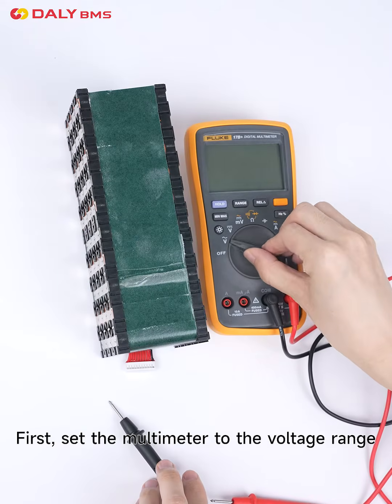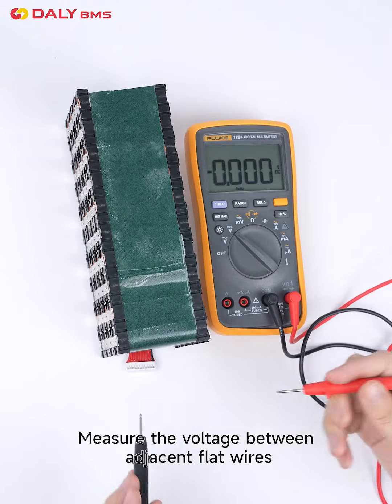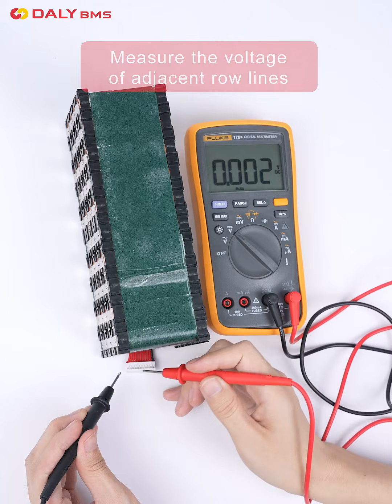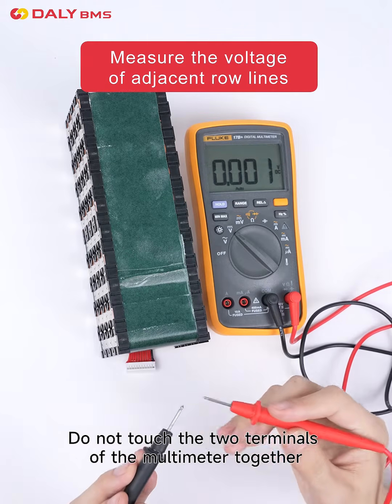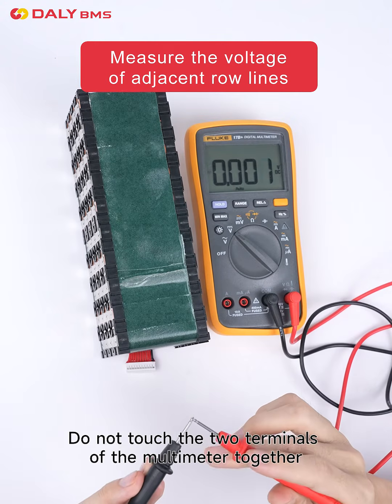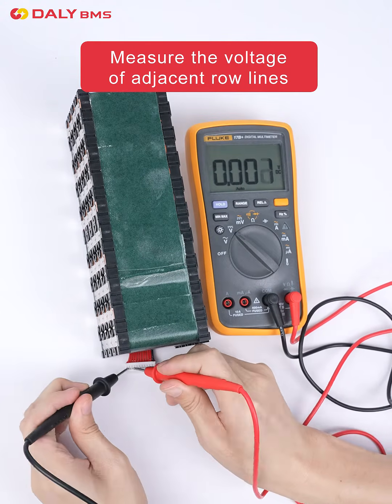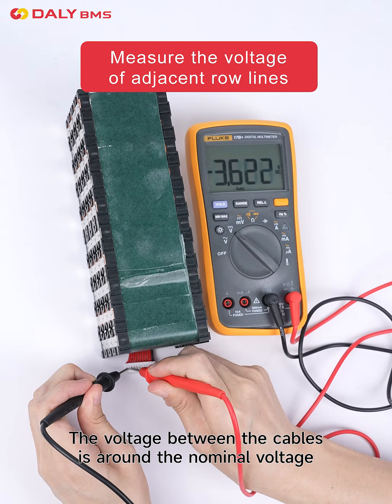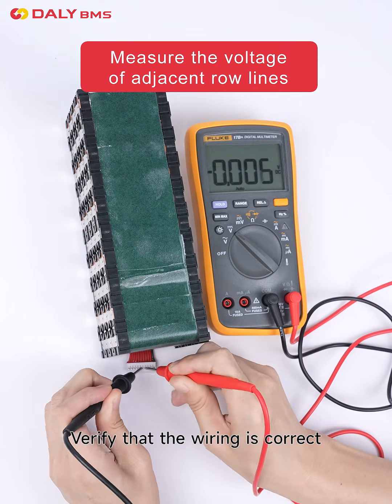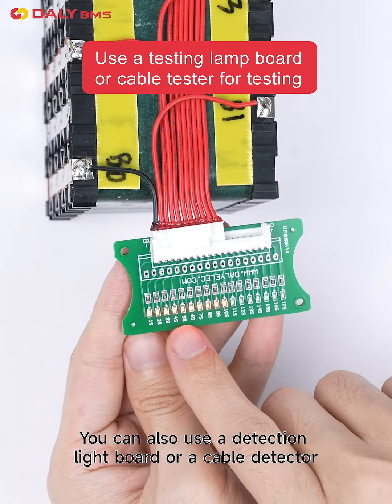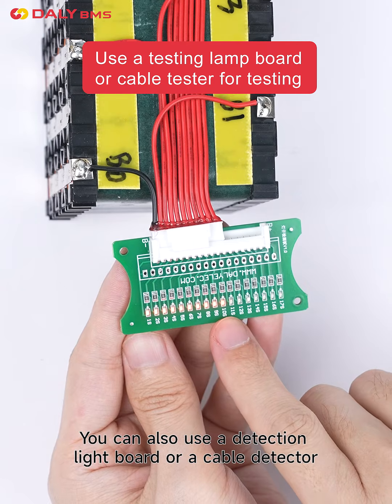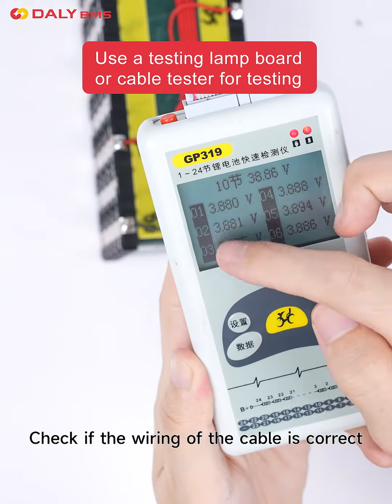First, set the multimeter to the voltage range. Measure the voltage between adjacent flat wires. When measuring the cable layout, do not touch the 2 terminals of the multimeter together to avoid short circuits. The voltage between the cables is around the nominal voltage. Verify that the wiring is correct. You can also use a detection light board or a cable detector to check if the wiring of the cable is correct.